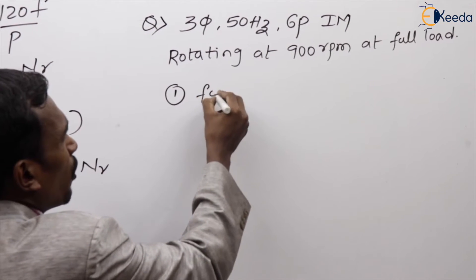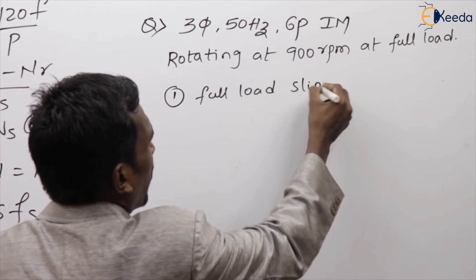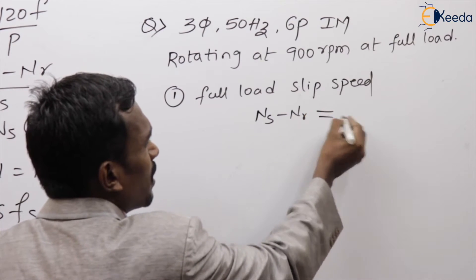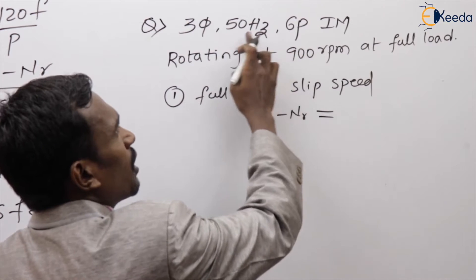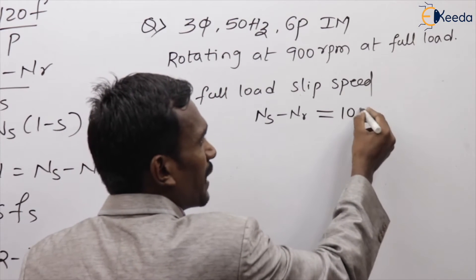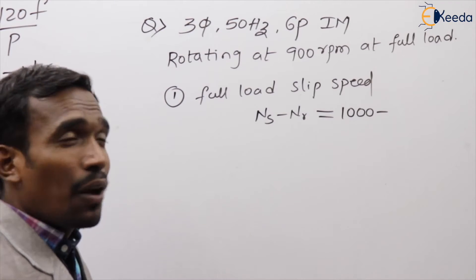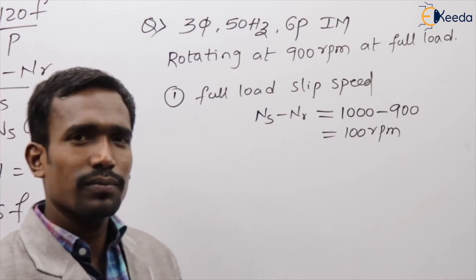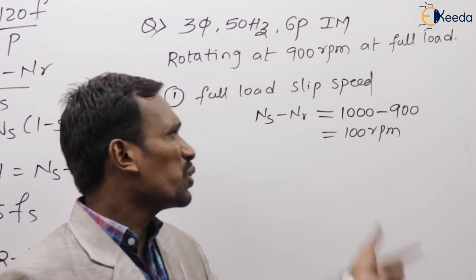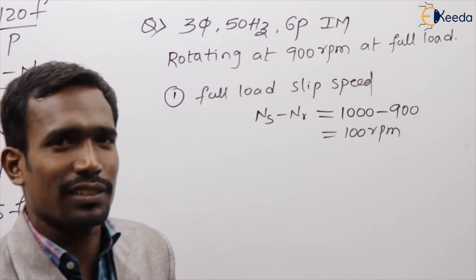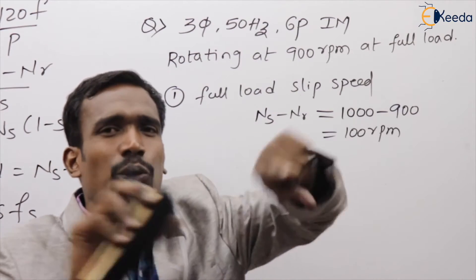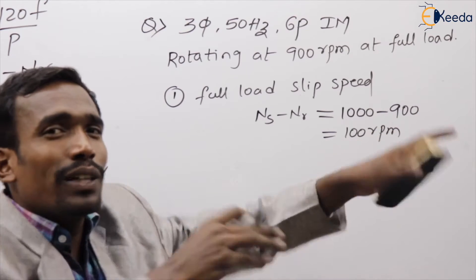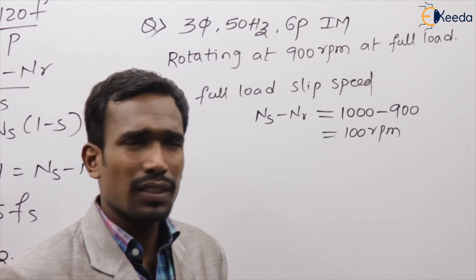First question: what is the full load slip speed? The formula is NS minus NR. For a six-pole 50 Hz machine, the synchronous speed is 1000 RPM. The rotor speed is 900 RPM. So the slip speed is 1000 minus 900 equals 100 RPM. Just by seeing the question we can tell the answer — six-pole 50 Hz is 1000 RPM, rotor speed is 900, so slip speed is 100 RPM.